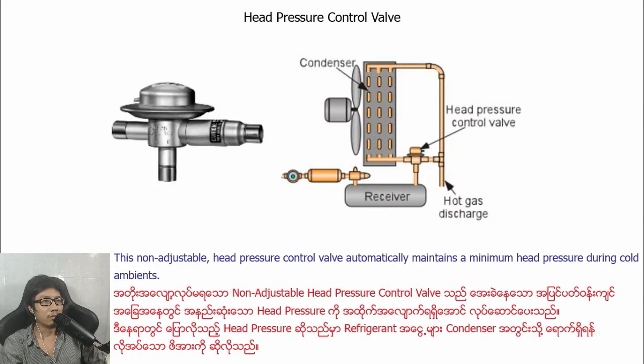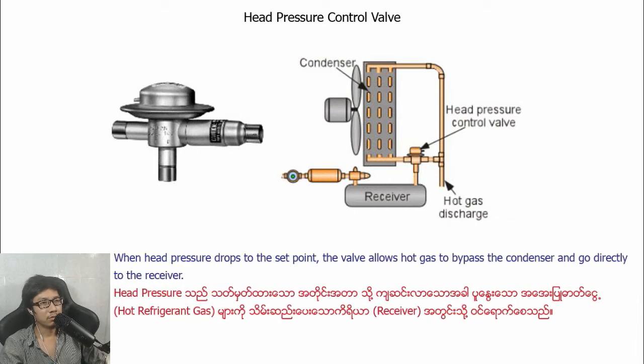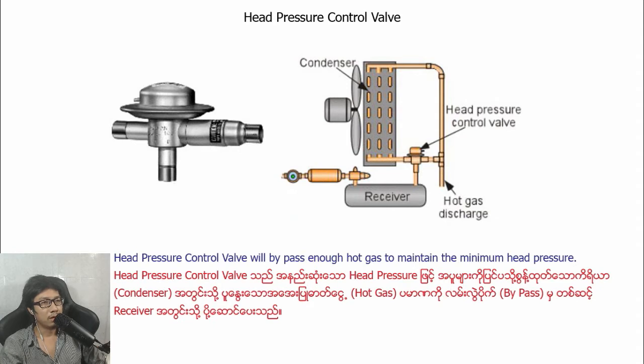Head pressure control valve. The head pressure control valve is non-adjustable. It automatically maintains a minimum head pressure during cold ambient. When head pressure drops to the set point, the valve allows hot gas to bypass the condenser and go directly to the receiver. The head pressure control valve will bypass enough hot gas to maintain the minimum head pressure.